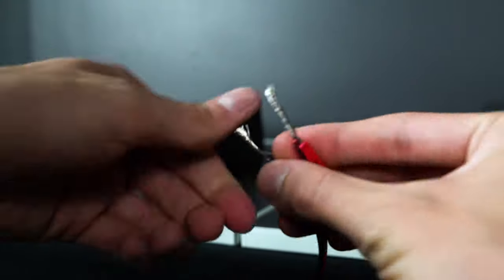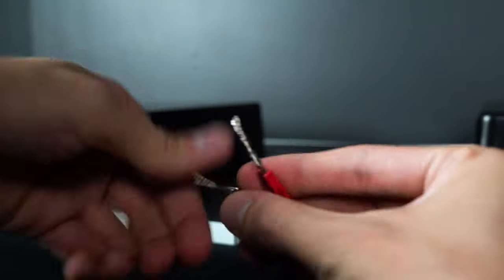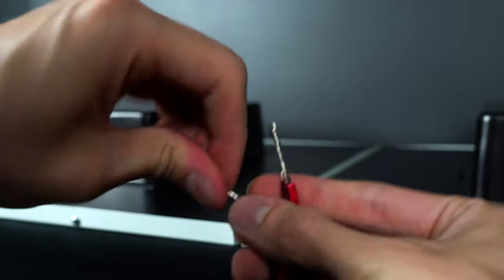And then once you have your speakers tapped, remember the wiring in 70-volt technology is very simple. It's parallel wiring, so it's positive to positive and negative to negative all the way down the chain. The great thing about these speakers and 70-volt speakers in general is you can mix and match them with other 70-volt speakers of all different shapes, sizes, and styles all tapped at different wattage amounts. And if you're using a multi-zone amplifier like I am, you can have different speaker chains in different rooms all acting independently on their own volume controls.